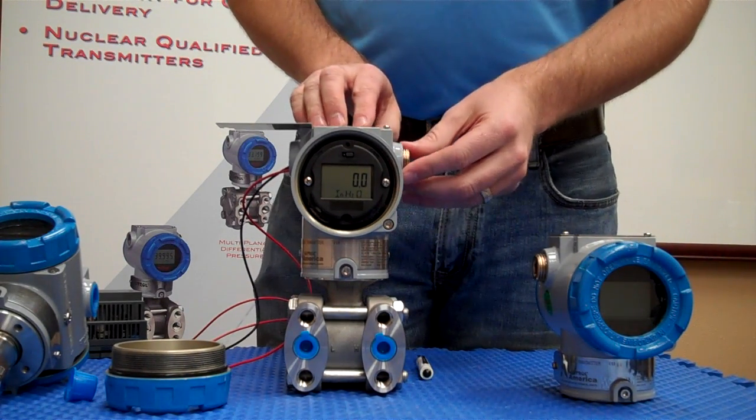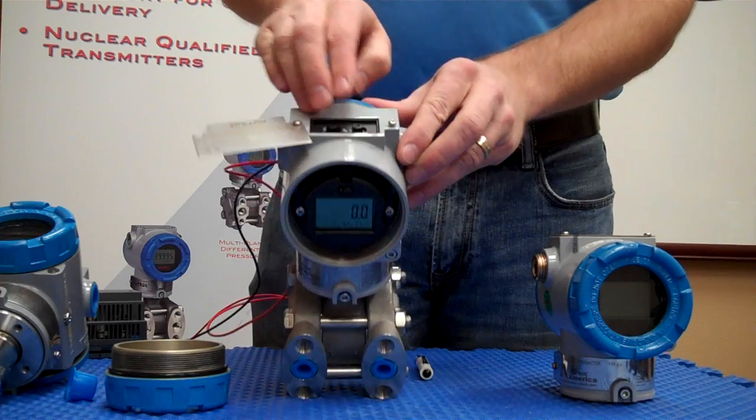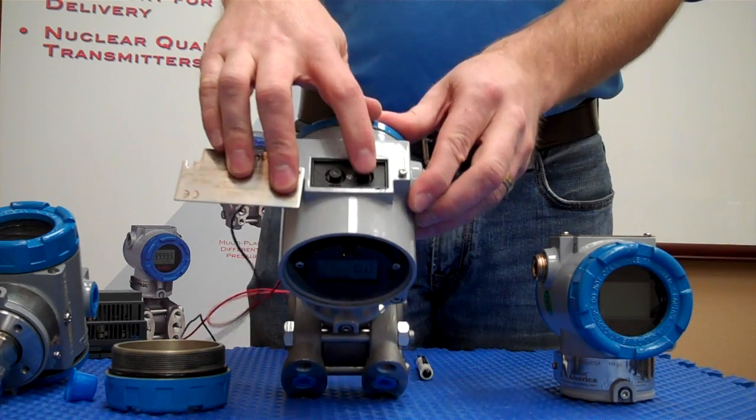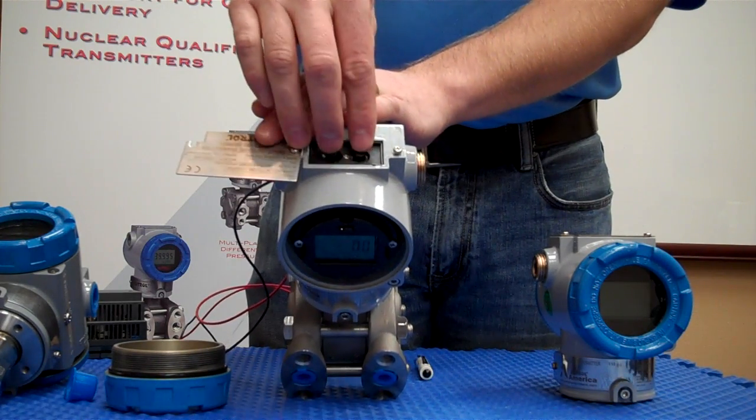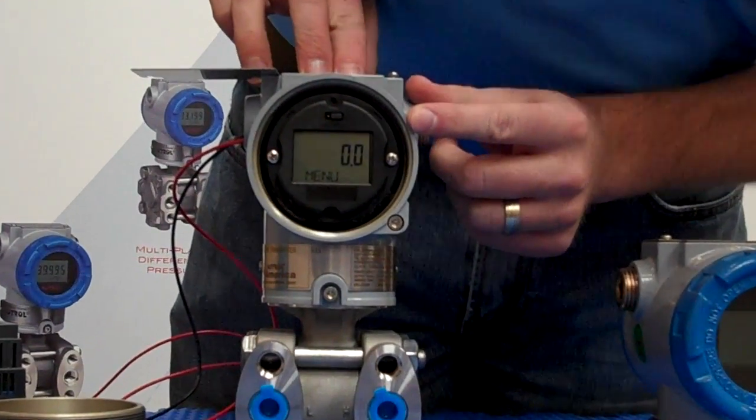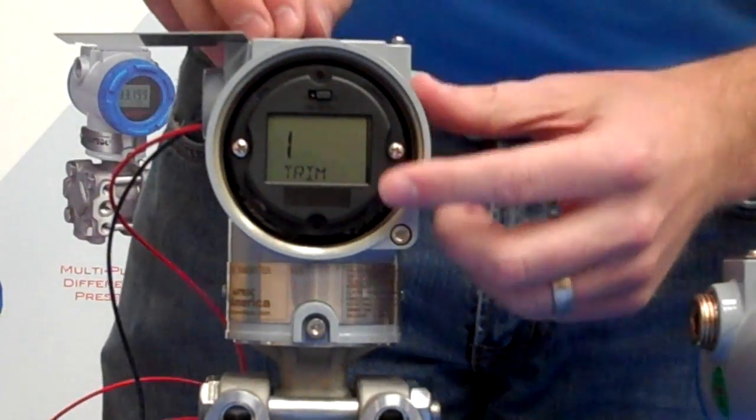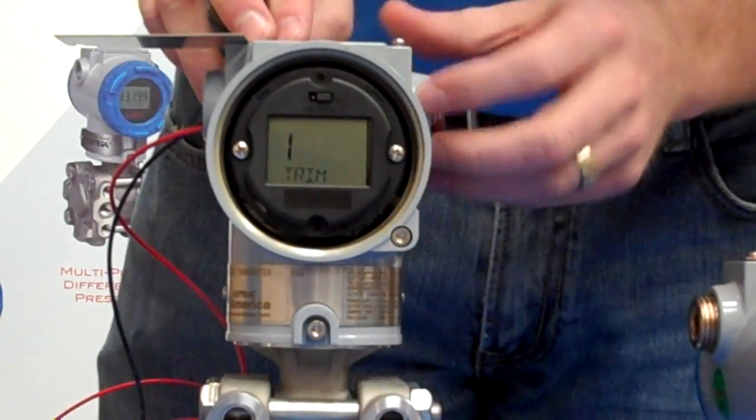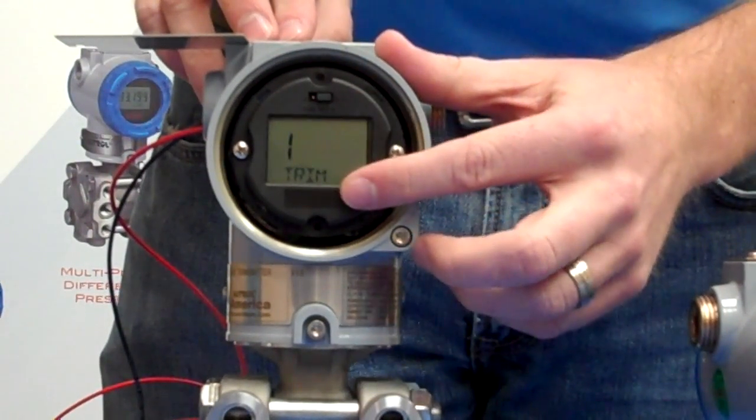First, to access the configuration mode, we push and hold both the zero and the span button at once, wait to see the change where it says menu, and release both of them. This is going to take us to trim, which is the first menu, and it's conveniently labeled.